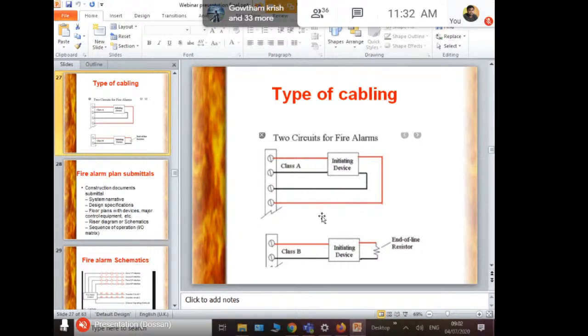drawing I've shown here. So if you see here, this is a smoke detector or whatever device we call, like the strobe, speaker, whatever it can be. From the control panel, we are giving a positive wire and a negative wire. So it is going to the device, coming out of the device, it is getting back to the panel. This is a class A wiring, and you will have multiple devices in it. I've just shown one device here.